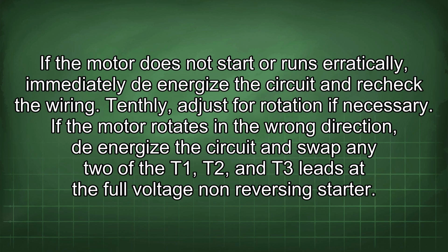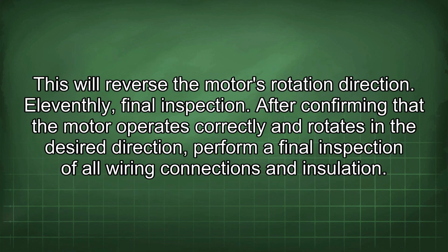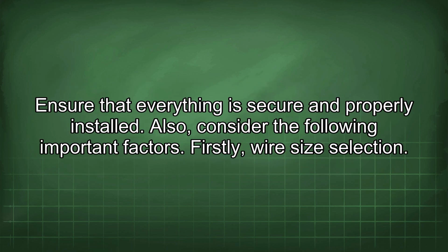Tenthly, adjust for rotation if necessary. If the motor rotates in the wrong direction, de-energize the circuit and swap any 2 of the T1, T2, and T3 leads at the full voltage non-reversing starter. This will reverse the motor's rotation direction. Eleventhly, final inspection. After confirming that the motor operates correctly and rotates in the desired direction, perform a final inspection of all wiring connections and insulation. Ensure that everything is secure and properly installed.